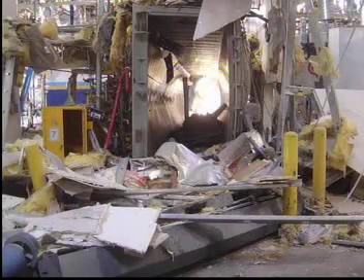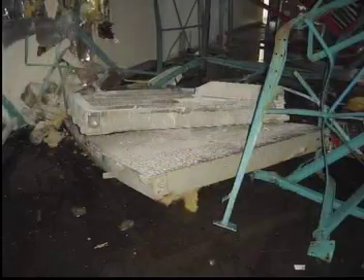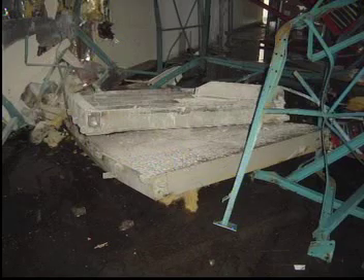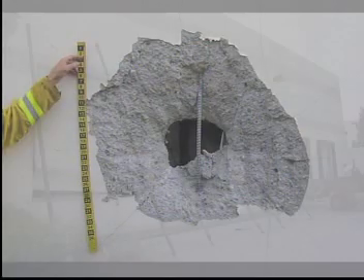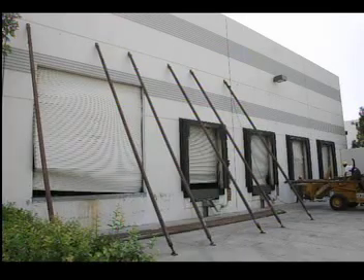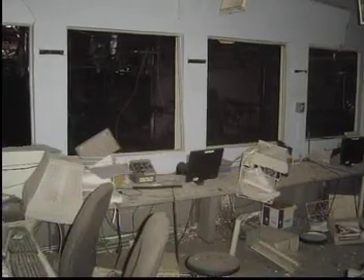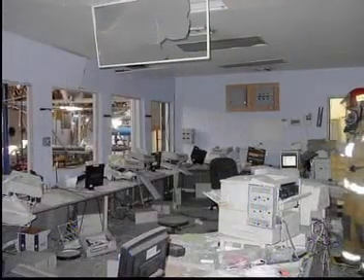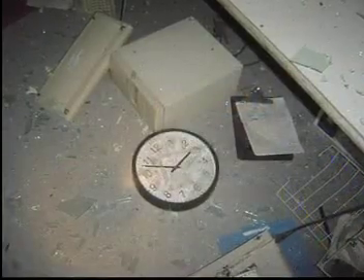It destroyed the sterilization chamber, bulging the chamber walls outward, blowing off both of the two-ton chamber doors, sending one of them 75 feet away, knocking out a hole in the north wall. The force of the blast caused widespread structural damage throughout the building. The control room was showered with flying glass from the windows. Debris, including the computers that control the process, littered the inside of the room.